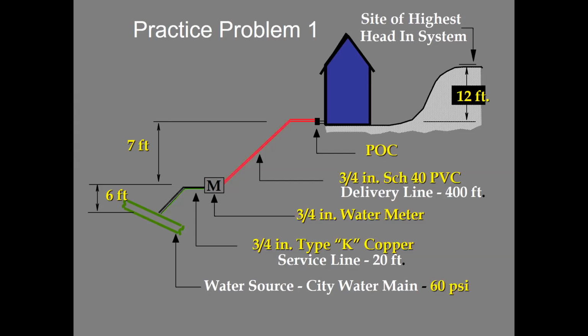Right. So then our PSI change due to elevation is going to be line number 2, which is 13 feet multiplied by 0.433 PSI. Should give us what? 5.63. Yep, actually, I think I got 5.62. It's like 5.629, but yeah. So 5.63 PSI.